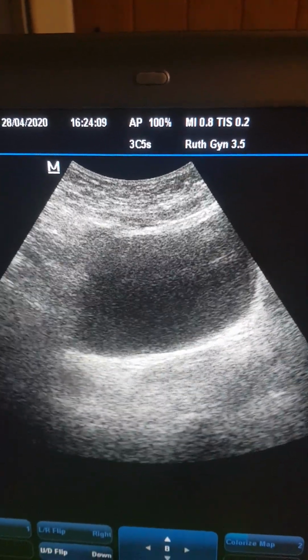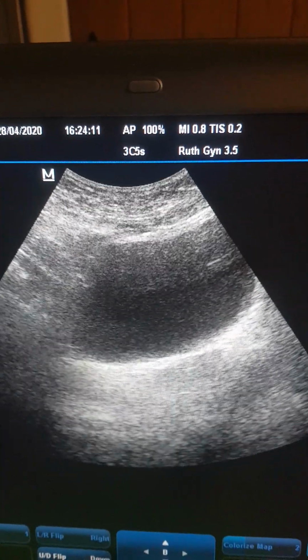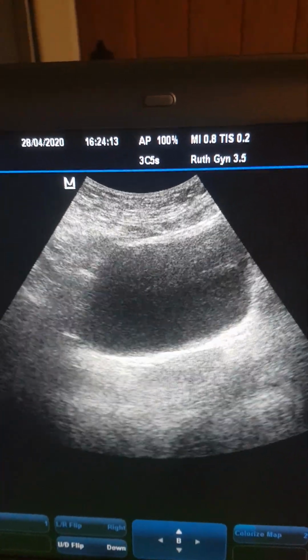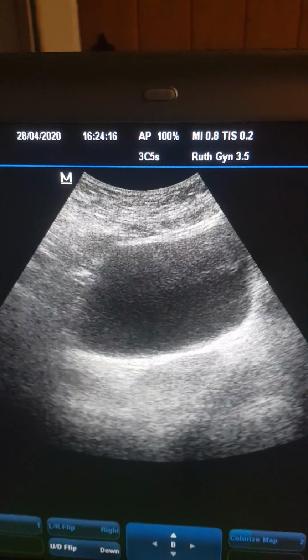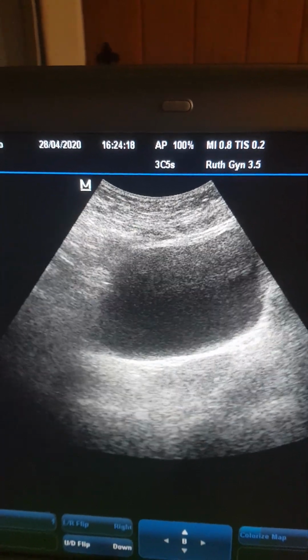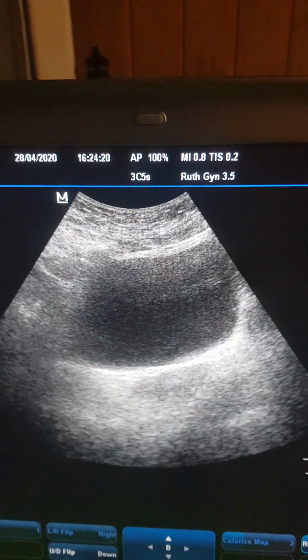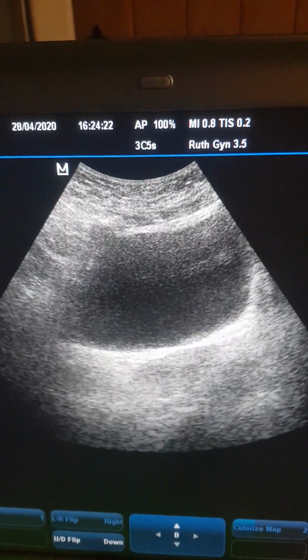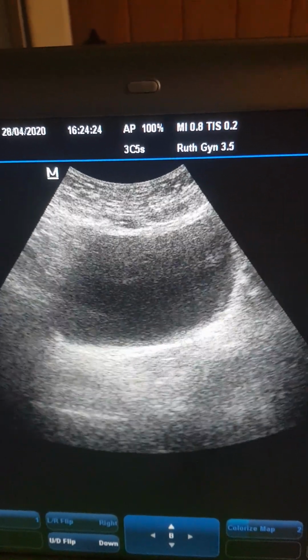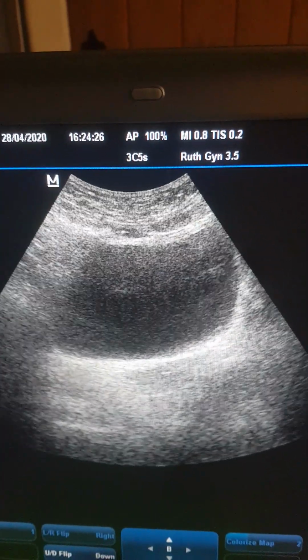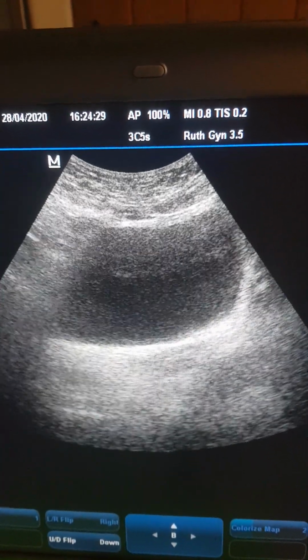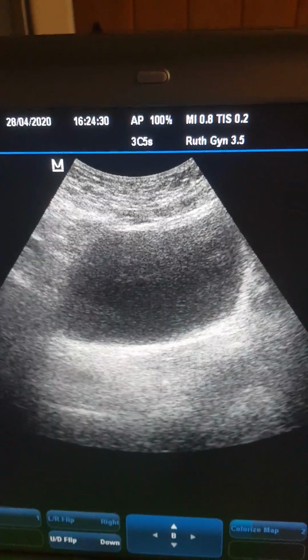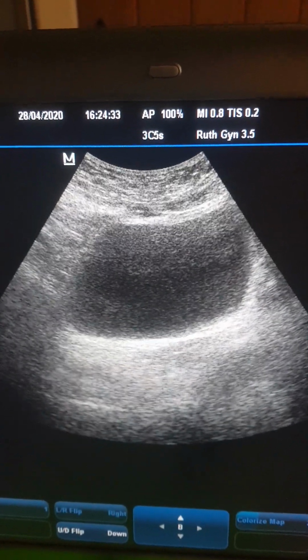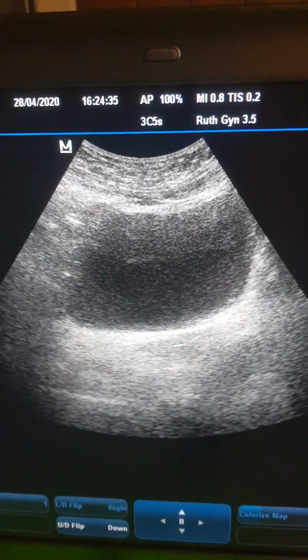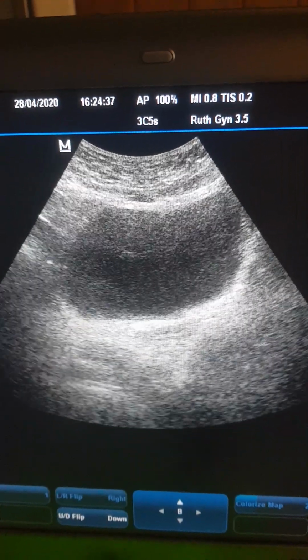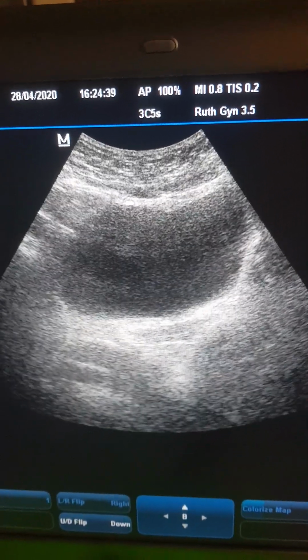And then in this position we could also do residual bladder volume. So if we were concerned about urinary retention, the machine has a preset to do residual bladder volume, where you can use the measurement function to measure this. We would then send the patient off to void, and then when they come back in, we would re-measure it. But we're not going to do that at the moment.